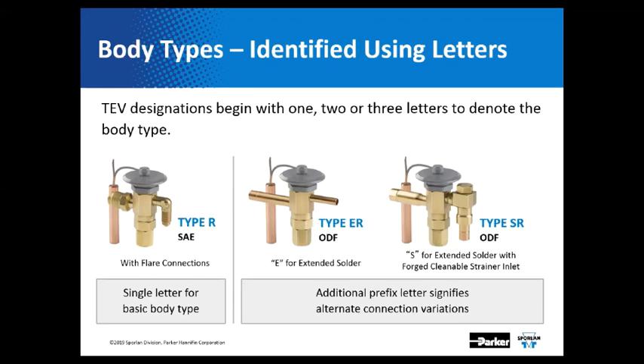The body type, or valve type, could be one letter, two letters, or up to three letters. The basic type R valve has flared connections. When you add E as a prefix, that means it has extended ends with ODF sweat connections. Over on the far right is the type SR — the S designates an inlet strainer, which can be easily serviced or cleaned. That's great for supermarkets, and great for any refrigeration that needs routine PMs.